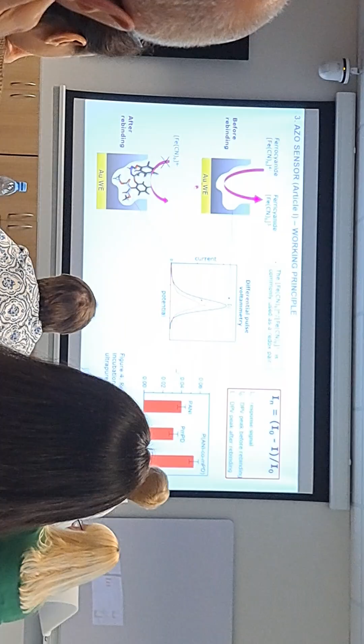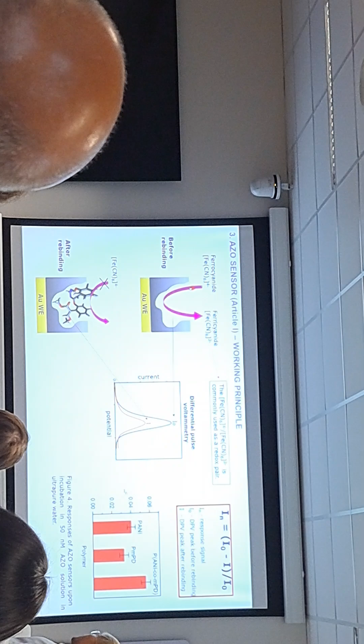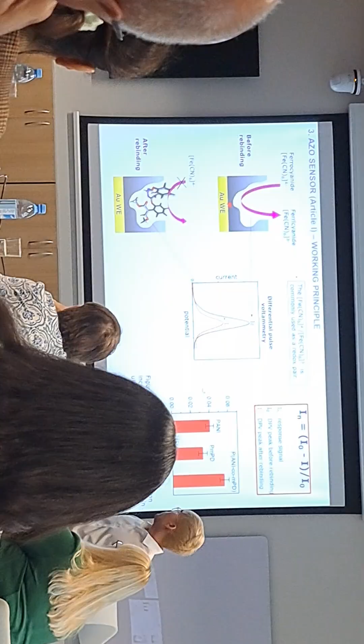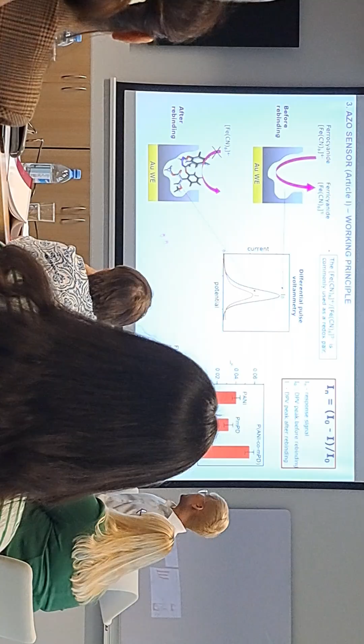And in the case of using a gold electrode together with the non-conductive target, this is how my sensor works. I need to put my sensor inside the solution with a redox probe. The idea is if I put into the system energy enough to oxidize ferrocyanide into ferricyanide, the electrons will flow into the system, resulting in a higher current peak. But if the non-electroactive target blocks here, it will be more difficult for this to extract the electrons into the system, resulting in a smaller current peak.